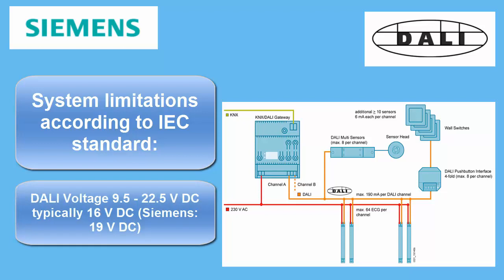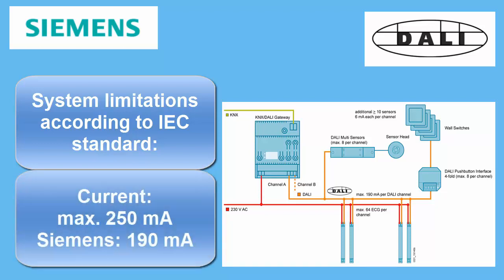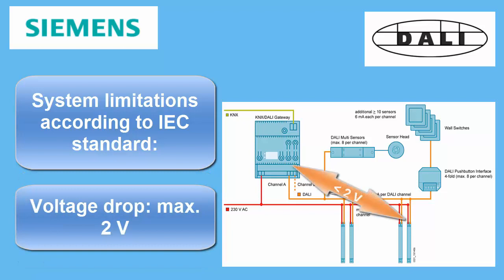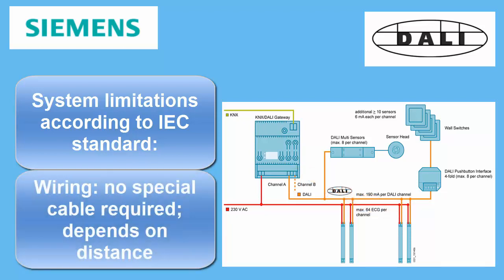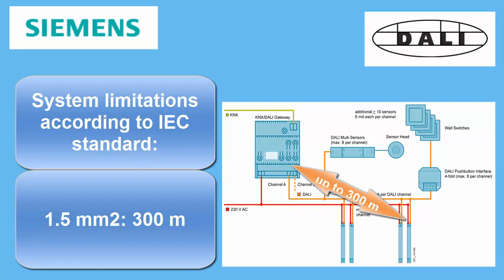The system limitations of wiring and addressing are as follows. The DALI voltage ranges between 9.5 and 22.5 volts DC, typically at 16 volts. The maximum current on a DALI line may be limited to 250 mA. The voltage drop between central controller and the ballasts may not exceed 2 volts. The maximum range of 300 m can be obtained using 1.5 mm² cable cross section; with 0.8 mm² cable, a maximum distance of 150 m can be reached.